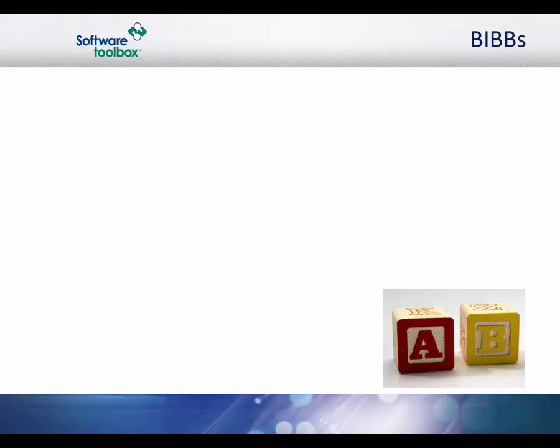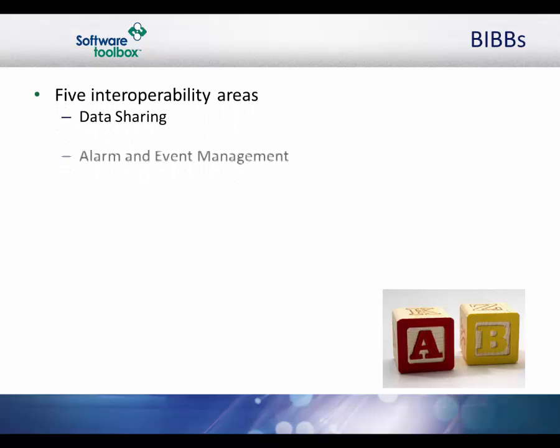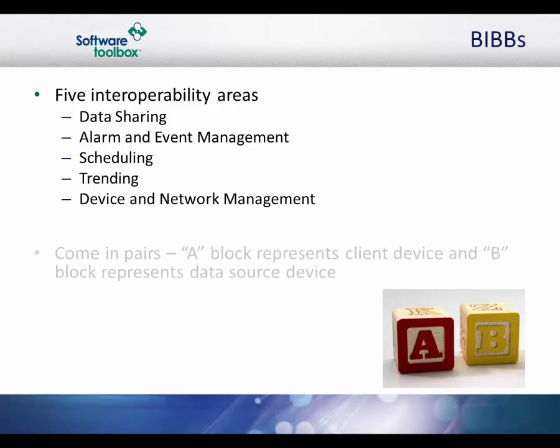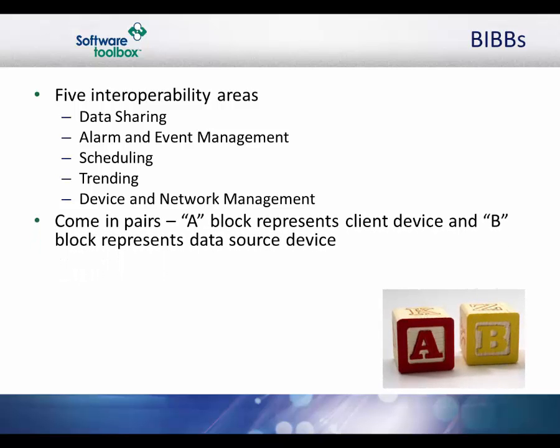There are five interoperability areas that represent the capabilities needed by building operators to perform the everyday activities of running a building. These include data sharing, alarm and event management, scheduling, trending, and device and network management. Eventually, the BACnet protocol was developed to incorporate these areas through the use of small building blocks so that, for each functional area, a specifier can select from a range of capabilities that best meet the intended application of the device.